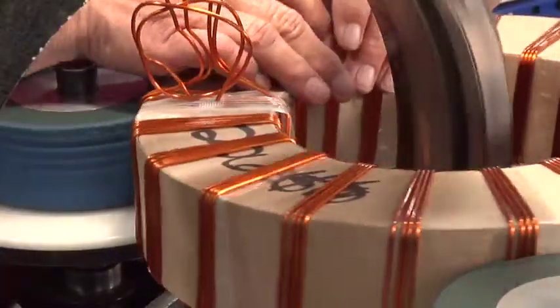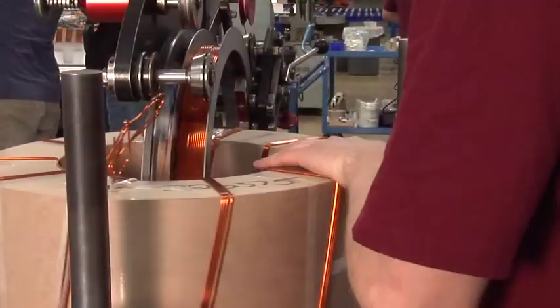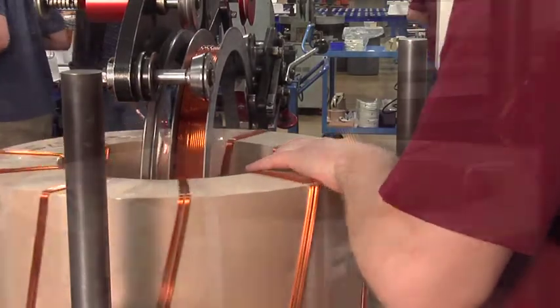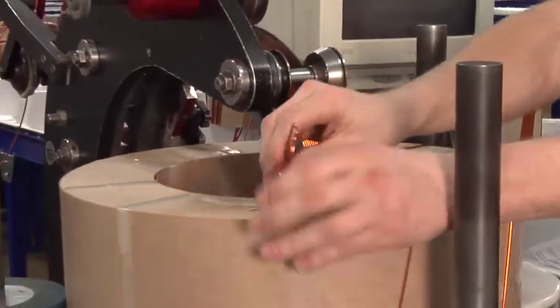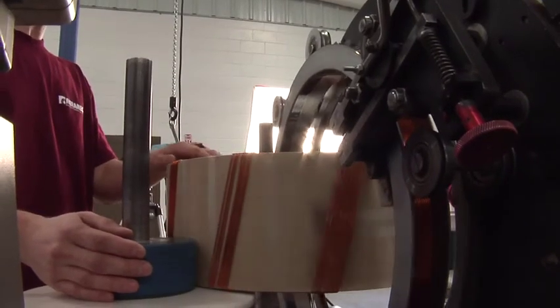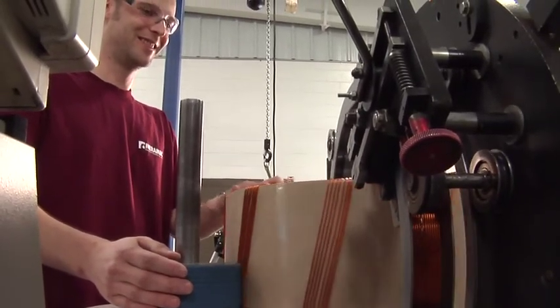The critical magnet wire winding process is performed by experienced craftsmen who use fully indexing automatic division toroidal winding machines. These equally distribute the secondary copper winding around the core. Winding machines are programmed based on design instructions which appear on computer displays at each workstation. All secondary windings are fully distributed around the toroid, which provides a low leakage reactance on each ratio. Single, dual, or multi-ratio configurations can be produced depending on the customer's design specifications.